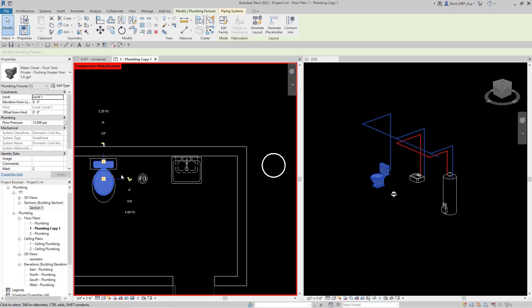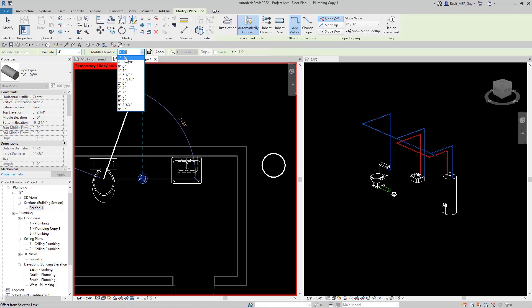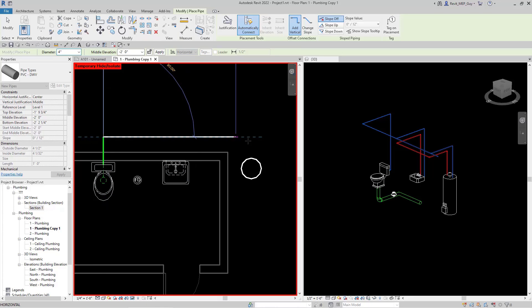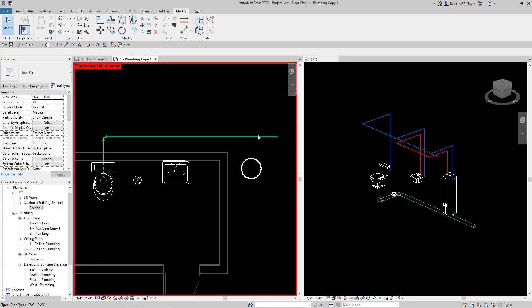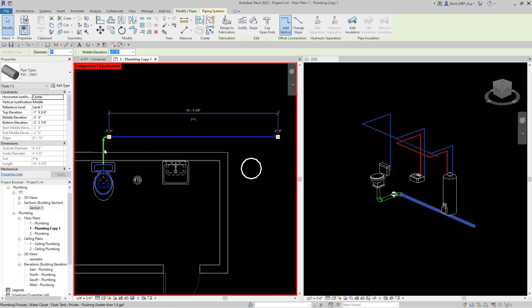I'm going to select my water closet because it's going to be my farthest fixture. I'll click the little 'create pipe' button with the P-trap icon — that's going to create some sanitary piping. It's good to always drop your sanitary about negative 2 feet. Let's run it out to here, make a right-hand turn to where it's leaving the building, then hit escape. Make sure the pipe type is set to PVC DWV — drain waste vent — so it draws in the correct fittings.